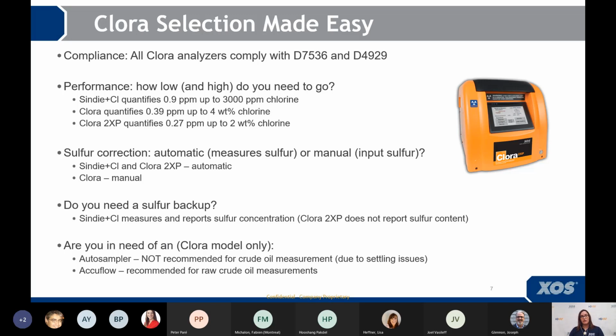The Sindie plus chlorine analyzer and the Clora 2XP have automatic sulfur correction. That is, the sulfur is measured at the same time the chlorine is being measured, and then the correction is done automatically. For the Clora, you actually need to know the concentration of the sulfur beforehand and input that before you measure the sample.